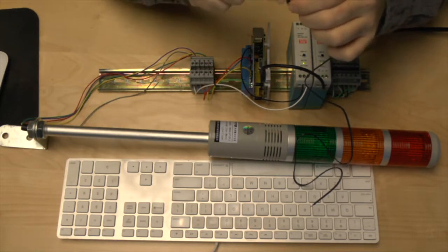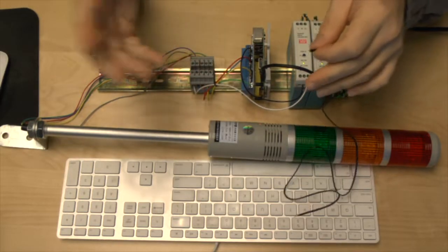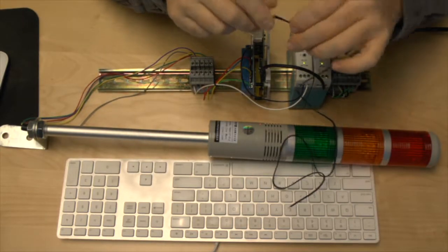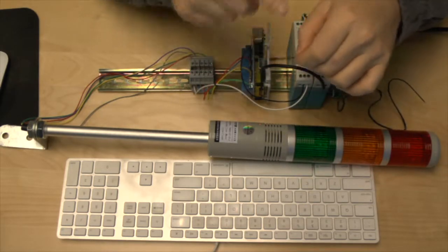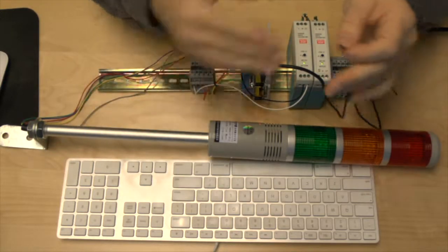And we can tell Sabe, look every minute or so, and if the motor's getting too hot, fire off a maintenance request. And that maintenance request may be attached to a different IoT node, which then turns on a yellow alarm. So that's an example of a slow poll. We look every minute, and we do something when the value is outside of a range.